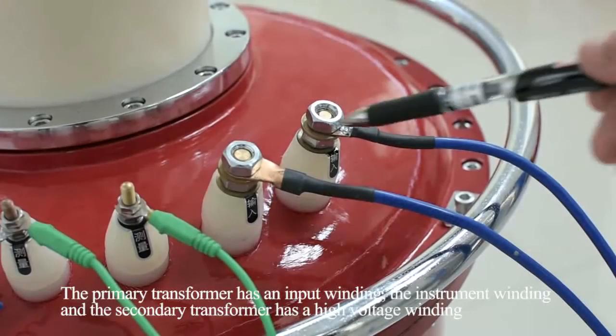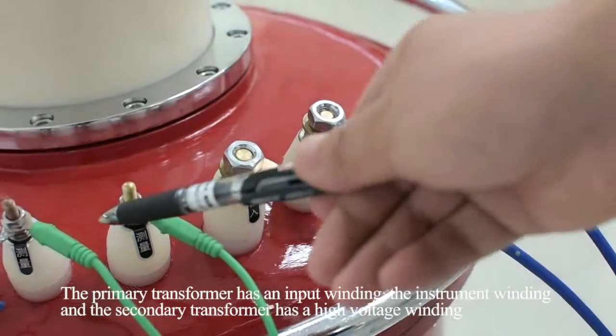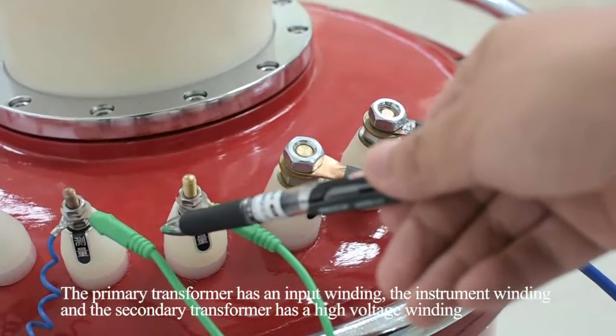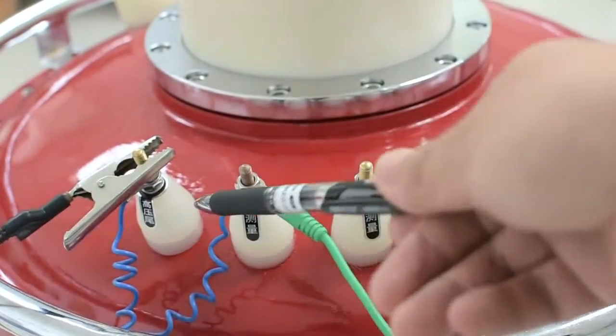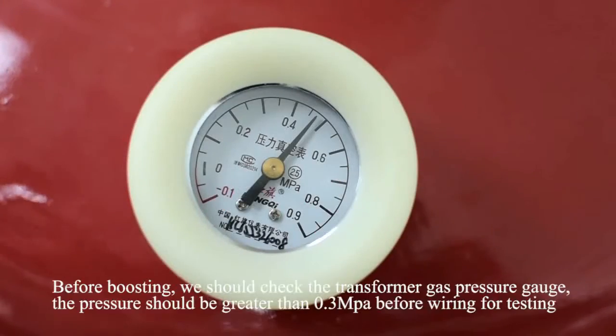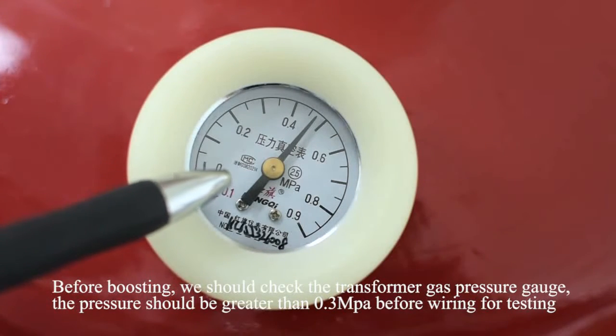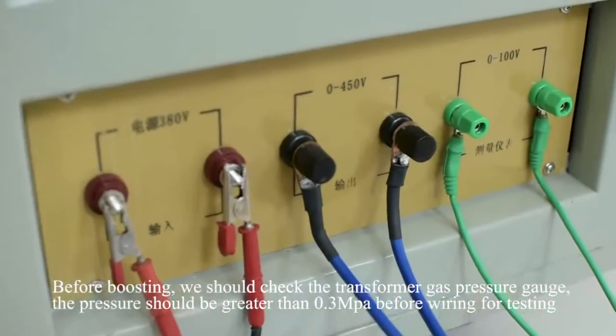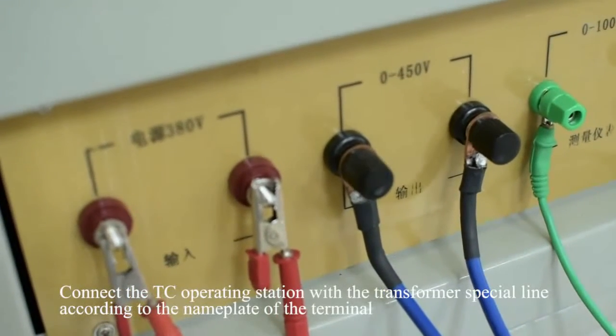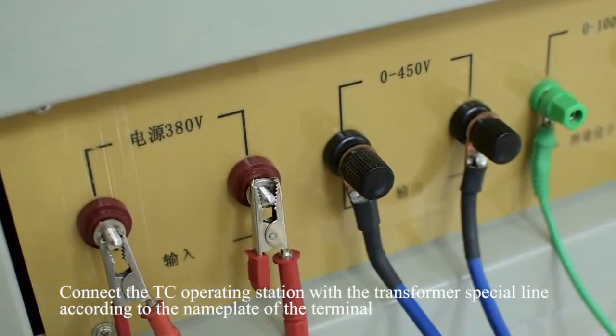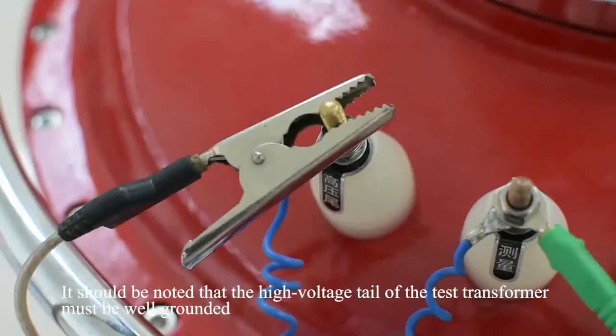The primary transformer has an input winding and an instrument winding, and the secondary transformer has a high voltage winding. Before boosting, we should check the transformer gas pressure gauge. The pressure should be greater than 0.3 MPa before wiring for testing. Connect the TC operating station with the transformer special line according to the label of the terminal. It should be noted that the high voltage tail of the test transformer must be well grounded.